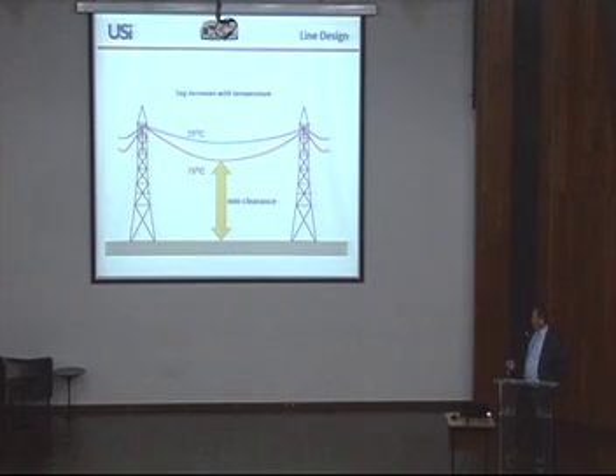DLR now, whatever you do with DLR and what you find as, let's say, thermal capacity of a line, the real capacity during operation and using DLR, this is always to be considered. Never heat up the conductor more than the maximum operating temperature.